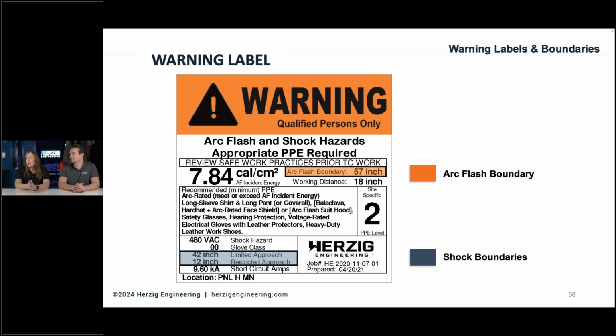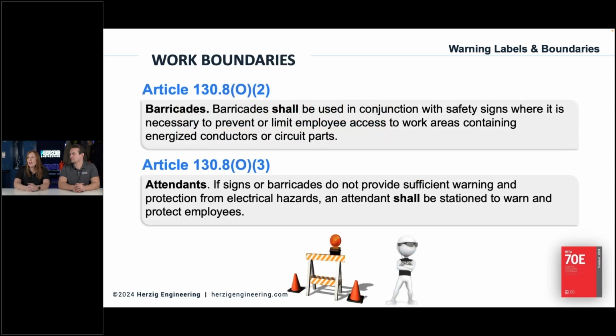Now, an argument I hear oftentimes is that the 70E is very specific - that if there's going to be exposed energized conductors or circuit parts, if they're working in an area with that, then there should be a barricade and/or an attendant. Shall - and bold.